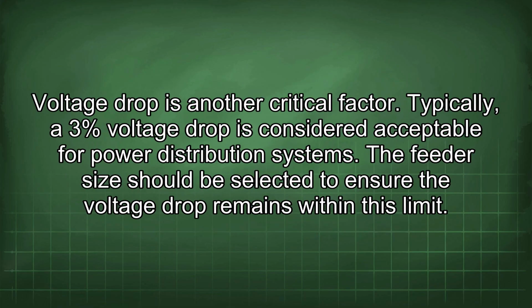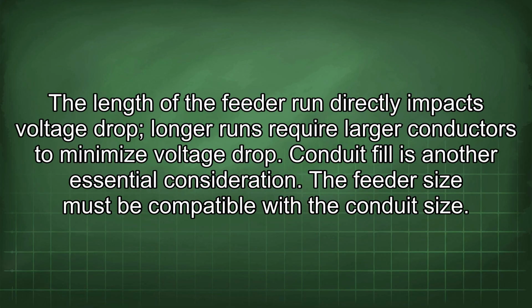Voltage drop is another critical factor. Typically, a 3% voltage drop is considered acceptable for power distribution systems. The feeder size should be selected to ensure the voltage drop remains within this limit. The length of the feeder run directly impacts voltage drop. Longer runs require larger conductors to minimize voltage drop.